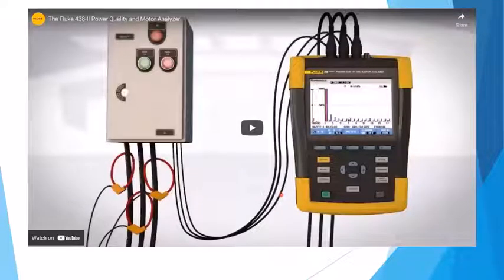So what I really recommend, and I found this metering to be extremely good, and if you are very heavily involved, I highly recommend you look closely into this meter, and I'll let it tell you a little bit more about what it can do. You're measuring those 3 phases in, and it's also got voltage probes that go across the power source and allow it to actually read with scoping what's going on.